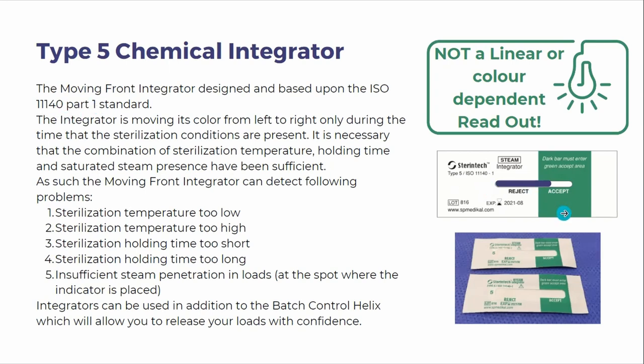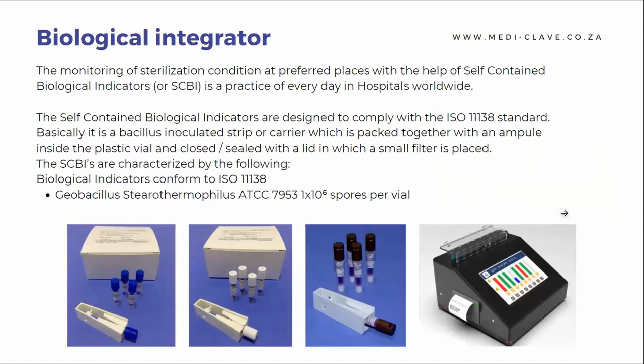We'll go on to the biological indicator. The monitoring of sterilization conditions at preferred places with the help of self-contained biological indicators is a practice of everyday use in hospitals worldwide. So it is a bacillus inoculated strip or carrier, which is packed into an ampule inside a plastic vial and is closed or sealed with a lid and a small filter.